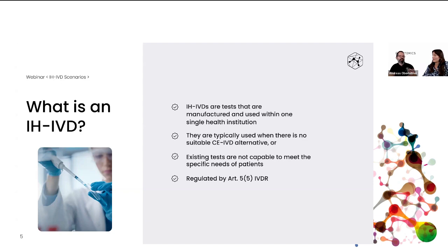Interesting. You said that it is regulated by the IVDR in Article 5.5, but there are also some differences, right? It's not the case that you need to follow the whole IVDR, because that is more towards IVDR manufacturers, but you have to at least focus on this article. There are, of course, differences: for an in-house device, there is no notified body involved. There is no pre-market approval formulated within these requirements. It's rather post-market control, let's say. Of course, the requirements differ a little bit. Still, it's an exemption, right? So you see it still as a privilege. Yes, exactly.